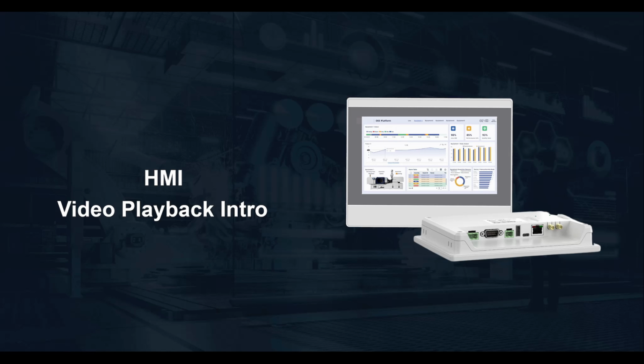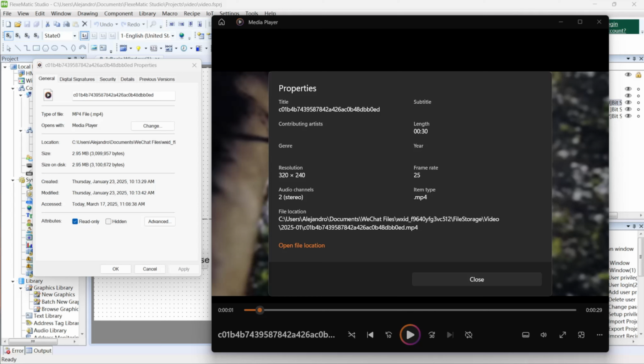Before we begin, it's important to note the file restrictions for the Media Player. The supported file formats include AVI, MP4, RMVB, and WAV. Additionally, the maximum file size allowed is 30 megabytes, and the frame rate must be below 24 frames per second. The resolution of the media file must also be smaller than the HMI's resolution to ensure proper playback. If these conditions are not met, the system will display an error.